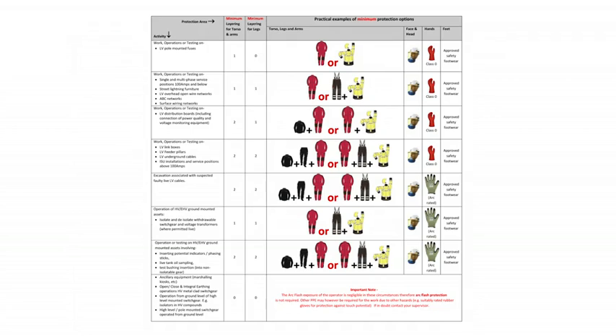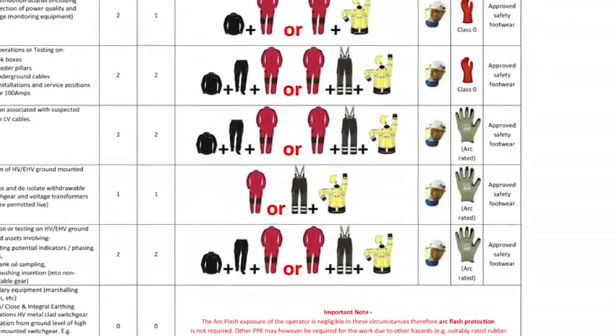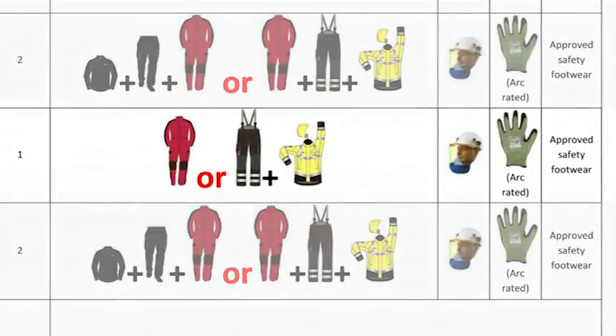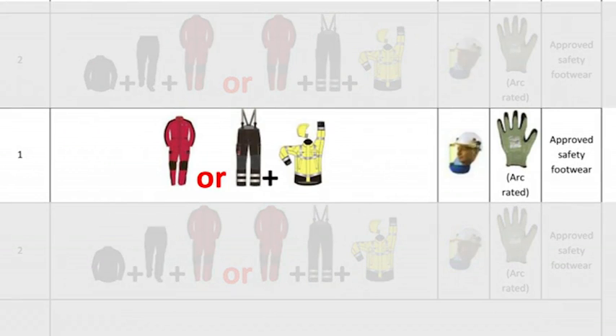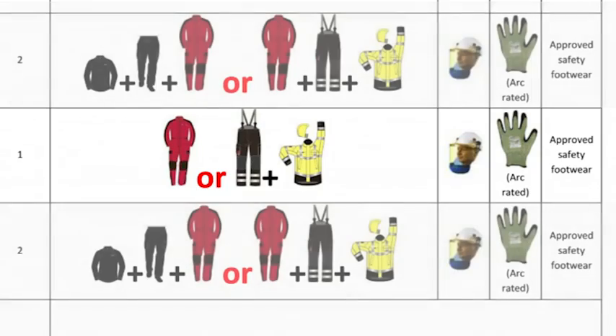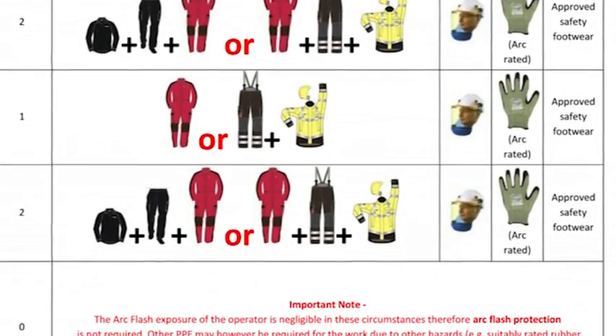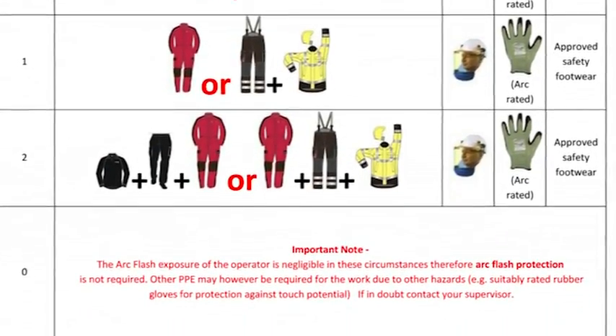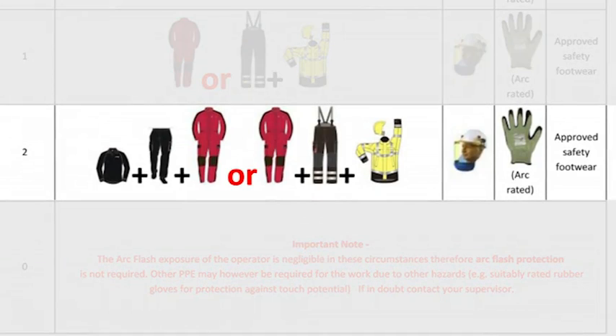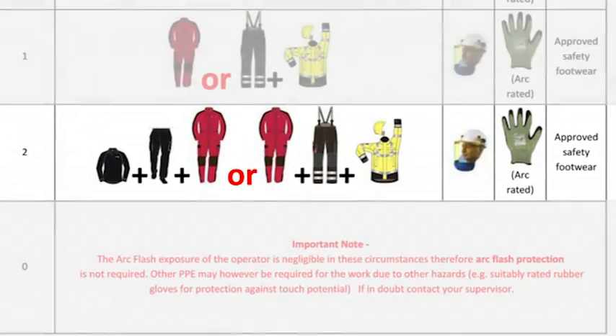You will be issued with guidance in the form of an arc flash PPE matrix. This will show you exactly which combinations of clothing you require to carry out each task. For operations of HV or EHV equipment, a single layer of protection is needed. This can be provided either by coveralls or your wet weather clothing. Some operations and testing on HV and EHV networks require a 2-layer combination to provide the necessary level of protection.